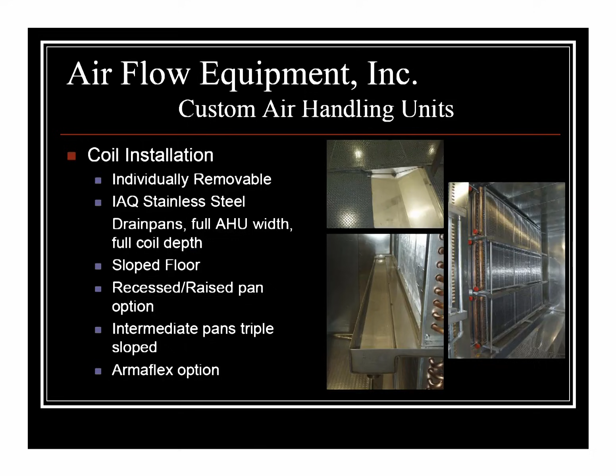All the coils are individually removable. Even when stacked three high, any one of the three can be removed without disturbing the others. We also put coil service plugs on both sides of the coil, on each side of the unit, so a removable plug can be taken out on both the header side and the return bend side. That's something we've learned over the years, it's very handy to have those removable plugs. If you want to pull a coil, you remove the plug and pull it out. Sometimes people ask why we do it on the return bend side as well.